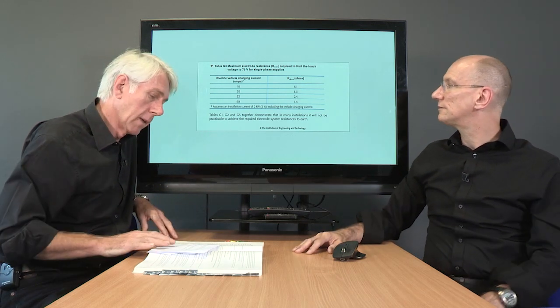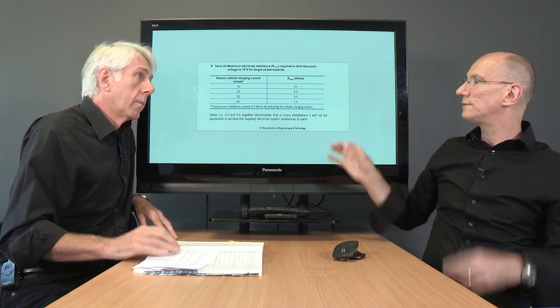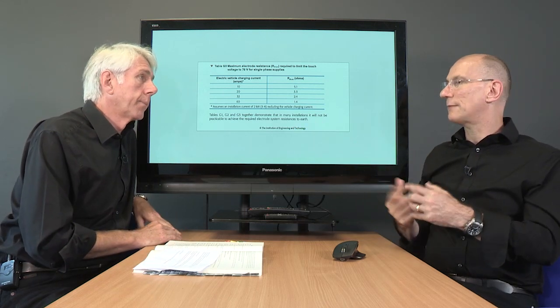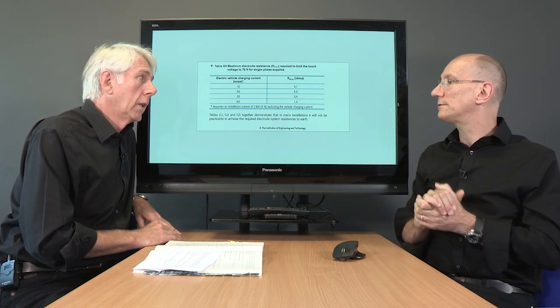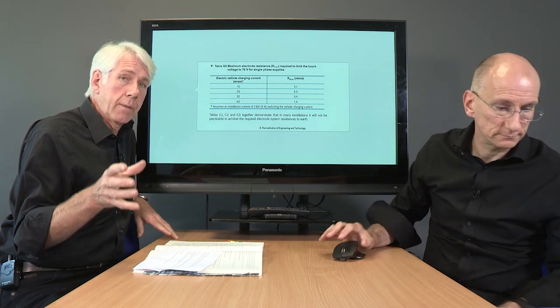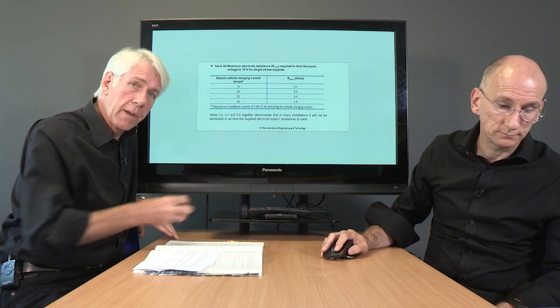And that's in addition to the other problems of banging in earth rods and potentially damaging supply pipes. Yeah, that is. You've got maintenance issues and corrosion, so yes. But this is to do with the 70 volts touch voltage that has come up, and we talked about that heavily in the other video. Yeah, so we're not going to go back over that. If you want to look at that, look at the other video on this subject. So we've got that one.